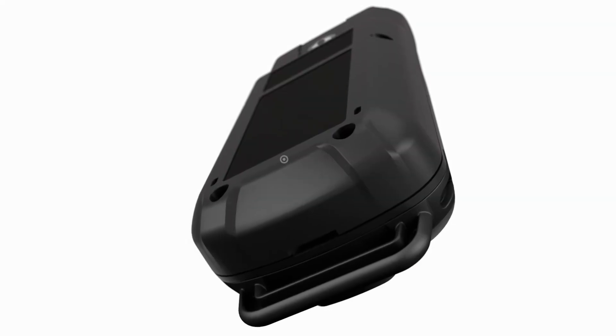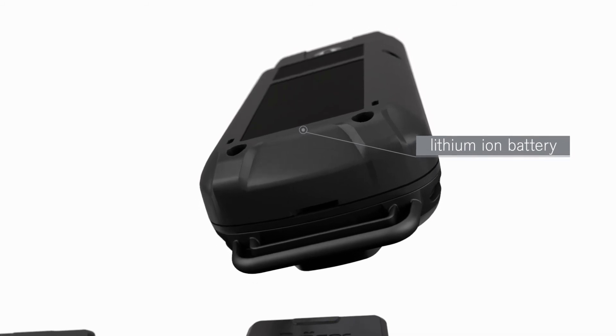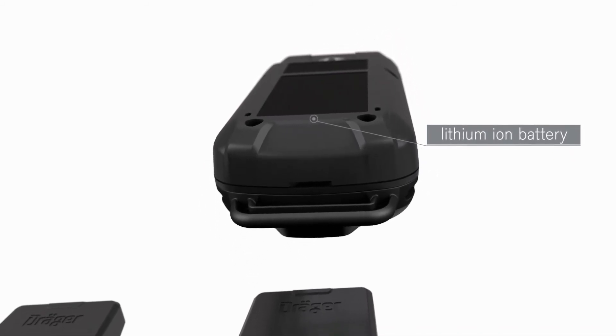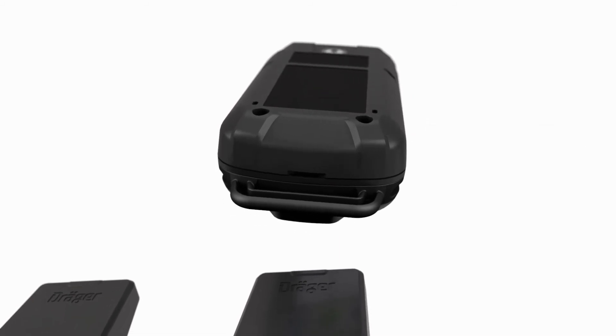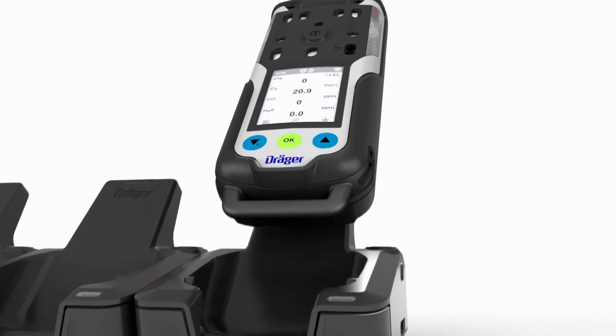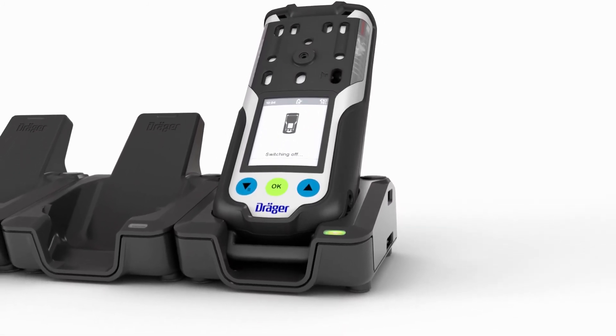The X-am 8000 is equipped with a rechargeable lithium-ion battery, which is charged inductively. Consequently, contaminations have no effect on the charging process and the contacts cannot become corroded. The gas detector switches off automatically as soon as it is placed in the charging cradle and the green LED on the cradle starts to flash.